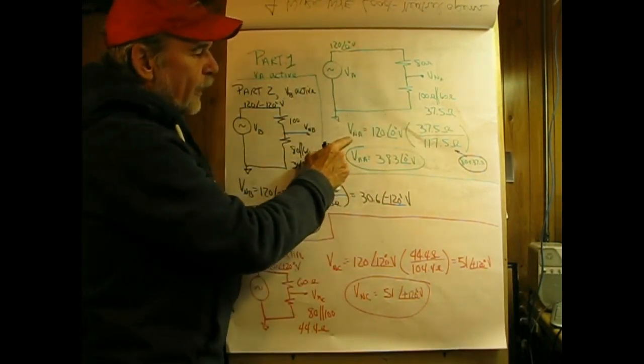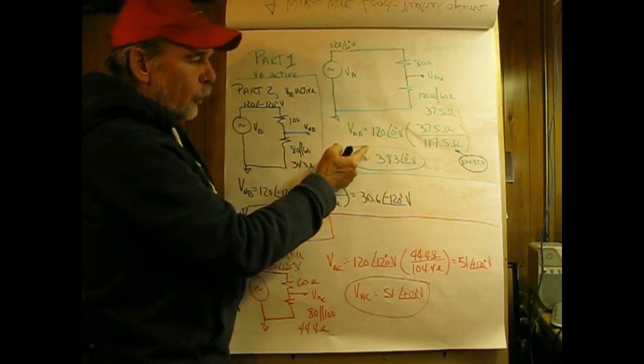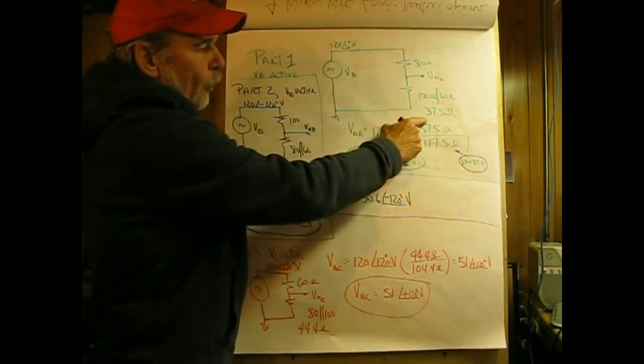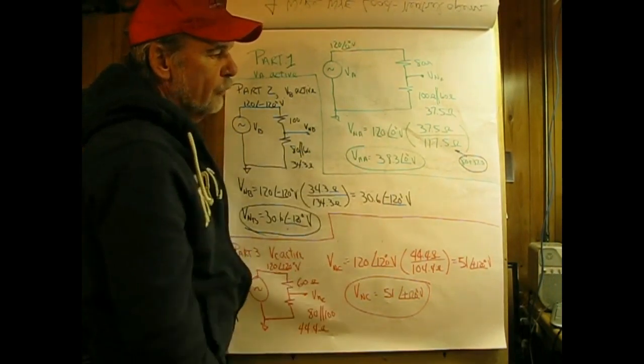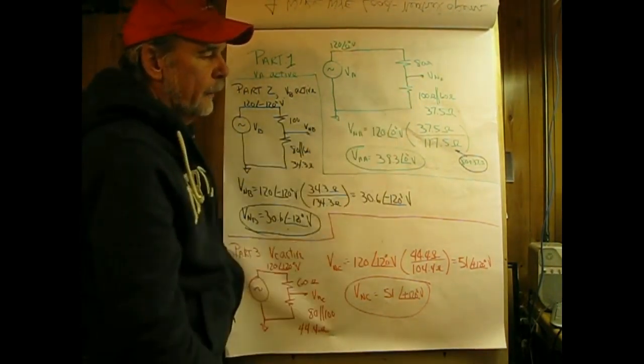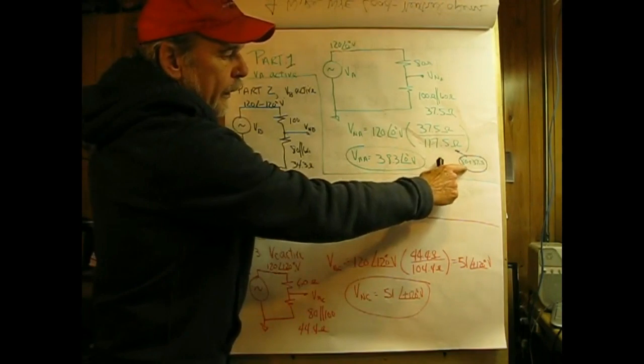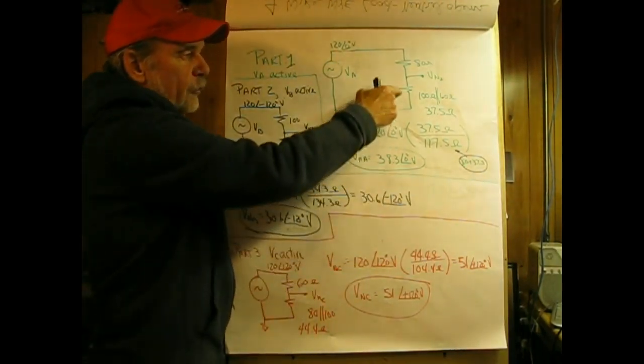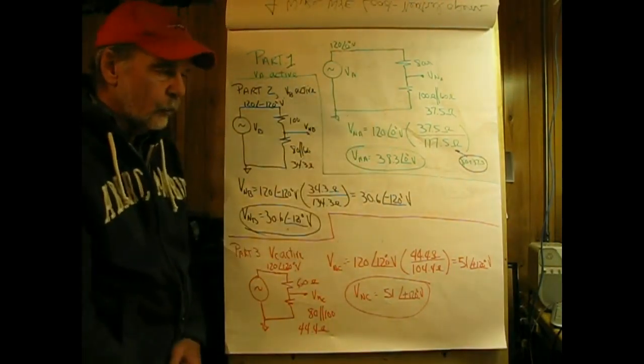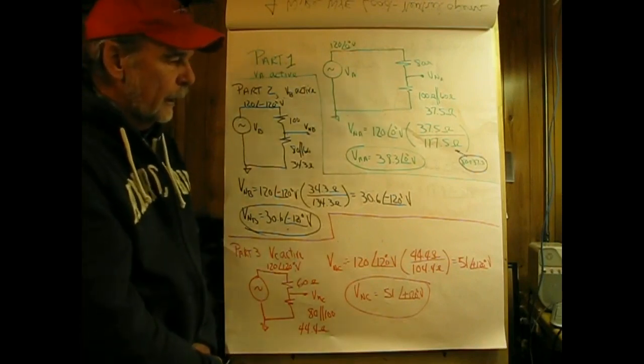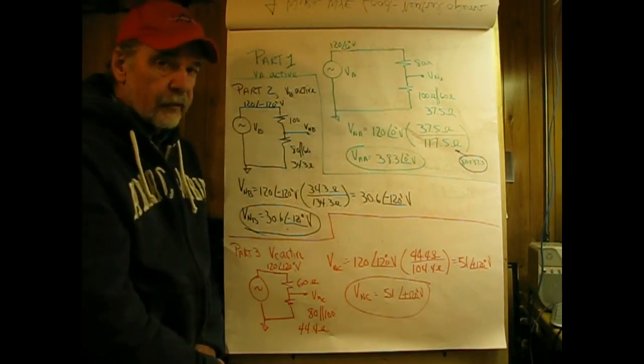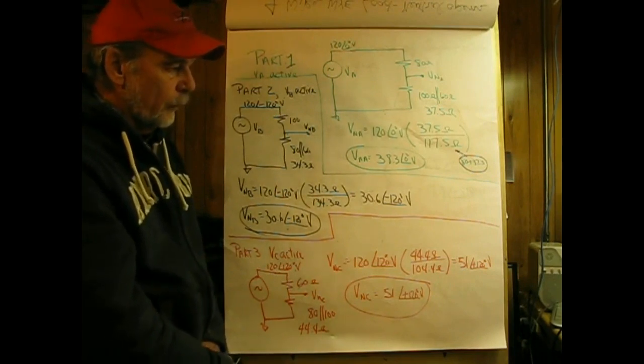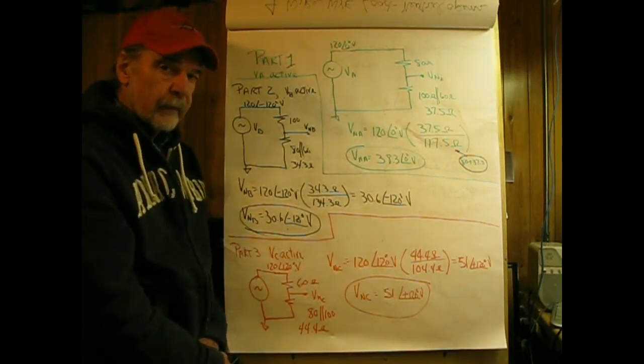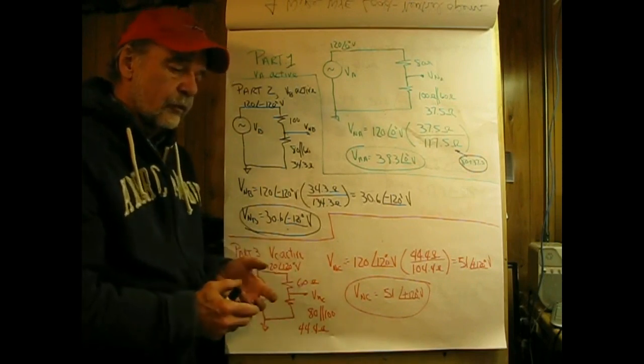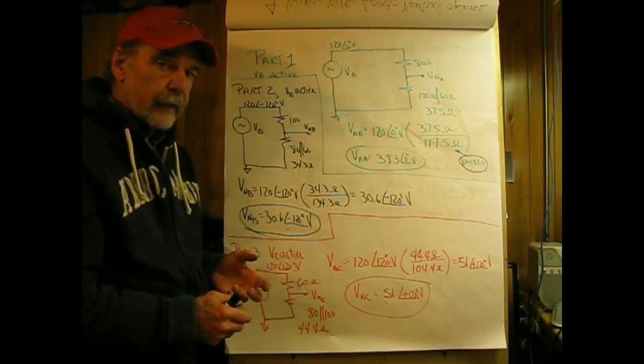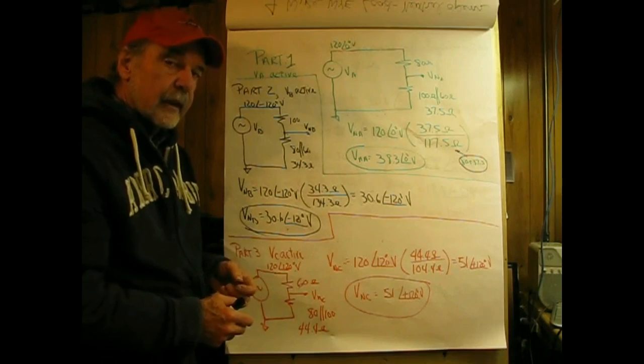Using the voltage divider, starting with V node A at 120, we want the voltage drop across the neutral line: 80 plus 37.5 ohms as the total resistance. V node A acting alone produces 38.3 volts at 0 degrees. A shifting neutral voltage can be very bad for appliances connected between phase and neutral.